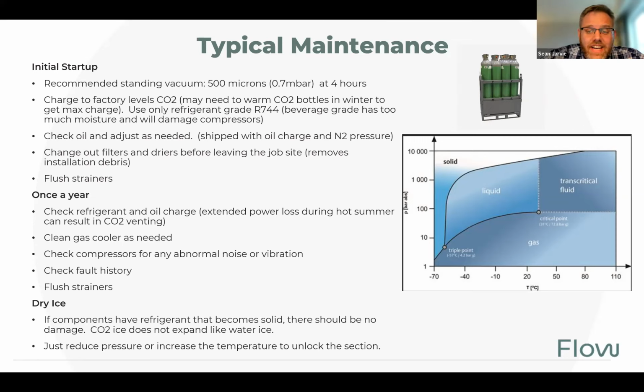After we get past all that, pulling shoes out of your strainers and leftover tools, these things are industrial grade, for lack of a better word, meaning that they can go a prolonged period. And with the receivers and our active oil management systems that are included in here, they can handle the shoulder seasons like a dream versus a lot of critically charged, very tight HFC systems. You're always going in and adding 5 pounds of refrigerant here, trimming it out there, adjusting the superheat there. There's a lot of touch points on a system like that. You won't see those same kind of touch points on a system like this.